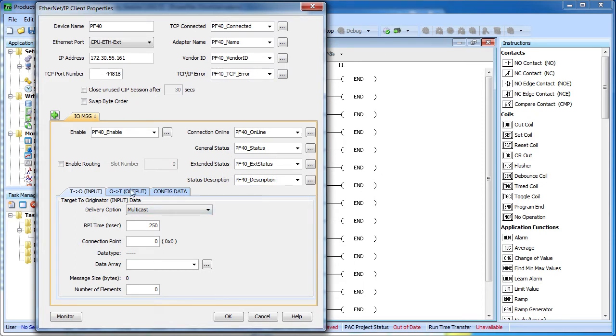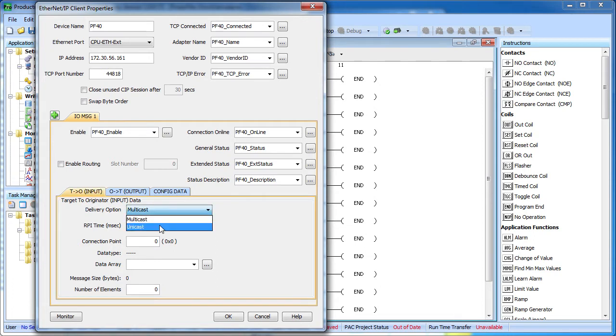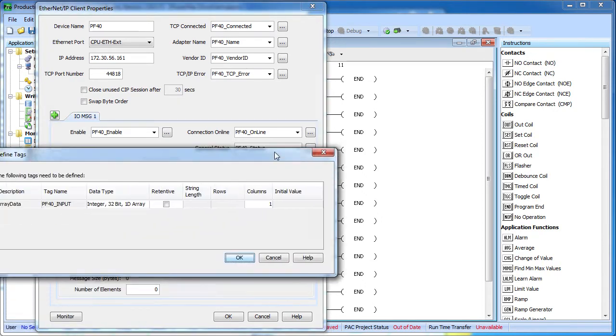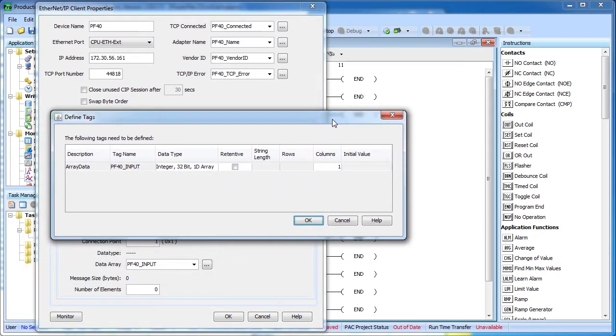Down here we set up the input, output and configuration data of the PowerFlex drive. For the input data, we want the PowerFlex drive to only send data to us so we'll select unicast. We'll have it send the information to us 4 times a second every 250 milliseconds, that's fine. And the connection point for this drive, which in the documentation they refer to that as the assembly instance, is a 1. We need to create an array to accept the input data from the drive so we give it a name.